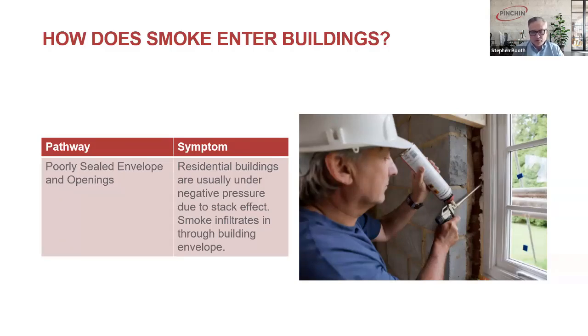For most commercial properties, we try to maintain a slight positive pressure, which helps keep wildfire smoke out. But in taller commercial properties, stack effect is really common—the lower portions of the building are under negative pressure to outdoors, while upper portions are under positive pressure. Air comes in at the bottom, is drawn up through the middle, and vents out the top. Even in those buildings, these pressure effects and small penetrations become a source for smoke to enter.